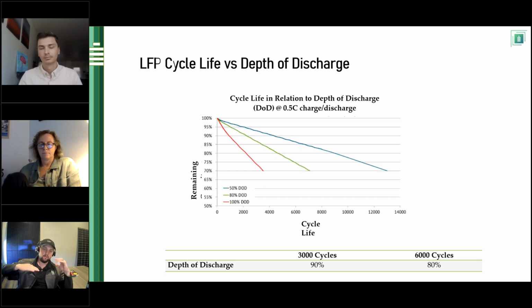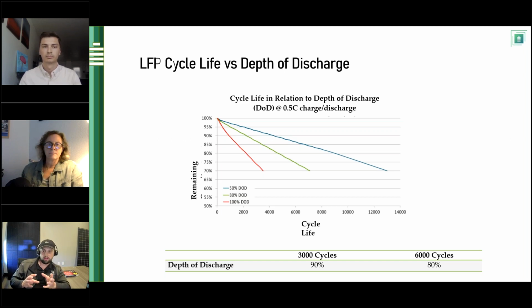In the event we have a backup generator, in the event we have the grid, ideally we'll target the usable energy needed from the battery bank as a factor of your consistent draw and your consistent load, and then we'll target that, right? But the point and takeaway of this is, just because you target that 80% depth of discharge, rarely is a system going to be hitting that 80% depth of discharge every single day, if designed correctly, unless that is your specific design principle.